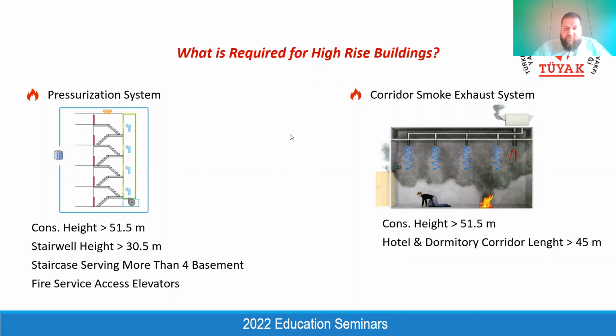And also for the hotel and dormitory buildings, it's a little bit different. Even if the building is not a high-rise, even if you have only a 2 or 3 story building, but if the building sectional area is large, it means if you have some long corridors more than 45 meters, you should either provide sectional zone doors, smoke-proof doors, or you need to provide a corridor smoke exhaust system. It's also decided by the architect. If the architect is okay with providing a door for each 45 meters, then you are allowed to omit the smoke exhaust system. But normally these doors are not preferred by the architects due to decorative issues. That's why in most of the hotel buildings, we have a corridor smoke exhaust system as well.